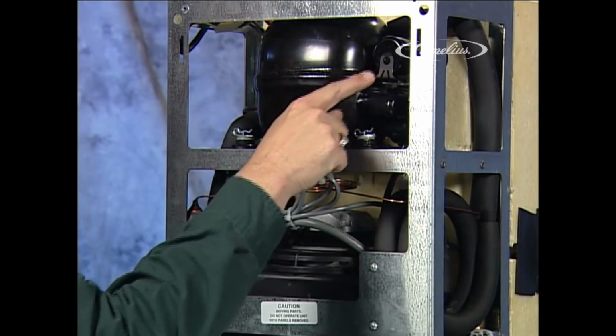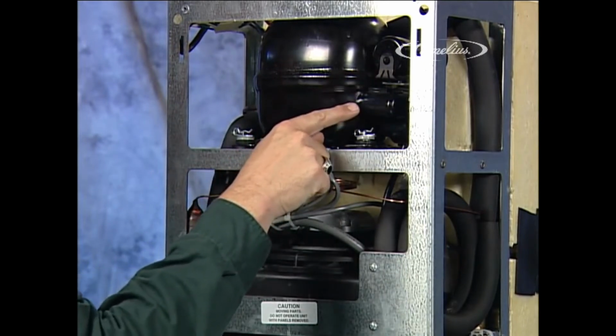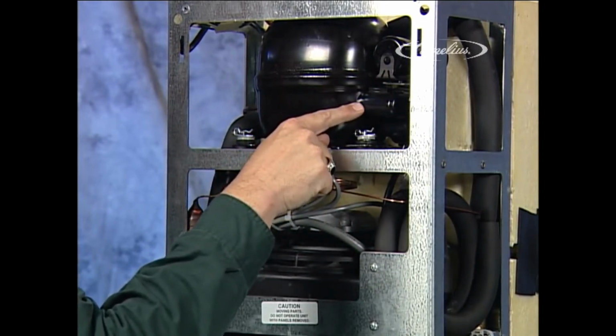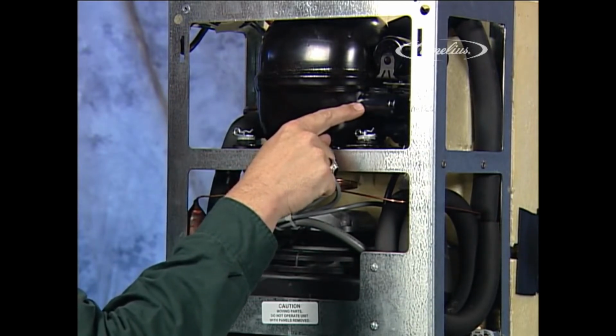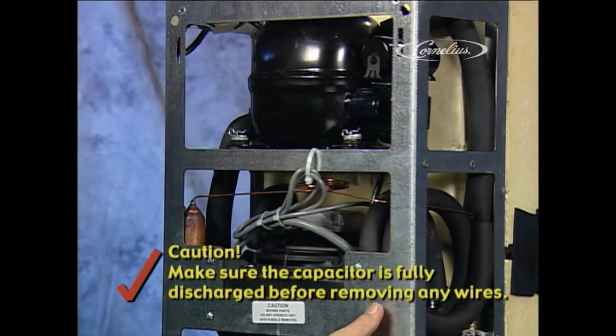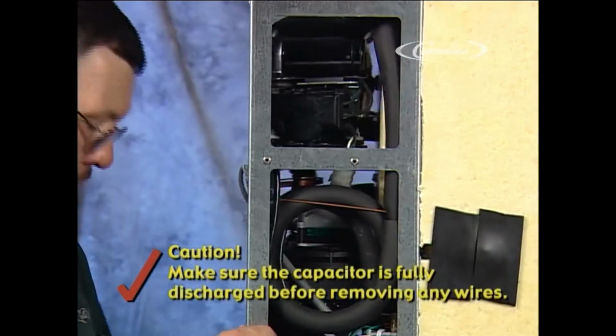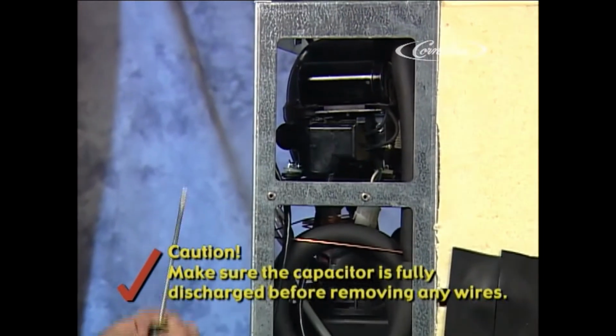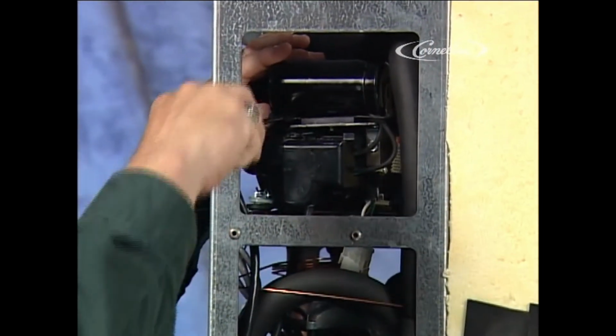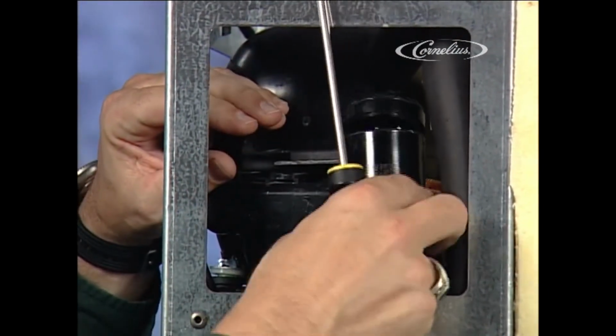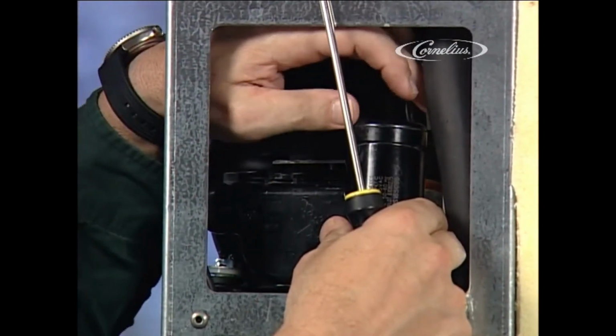If the compressor attempts to start but is unable to because of a bad start capacitor, you will hear it tripping out on the overload under this cover. It will be a metallic sound about every 4 to 5 seconds. Caution! You need to be sure the capacitor is fully discharged before making any attempt to remove the wires. It is best to use a screwdriver with an insulated handle placed across the posts. If the capacitor is good, a small spark will occur.